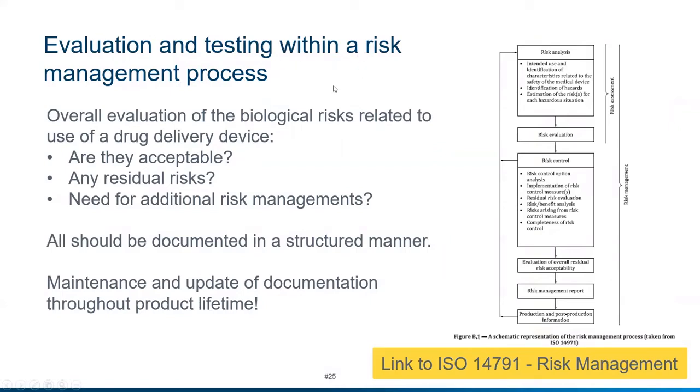Then you should evaluate your overall biological risks as part of the risk management process. So you need to consider, based on your test results, are the biological risks related to use of the device acceptable? Are there any residual risks, and do we need to do additional risk management? And here there's a link to the activities under ISO 14971.